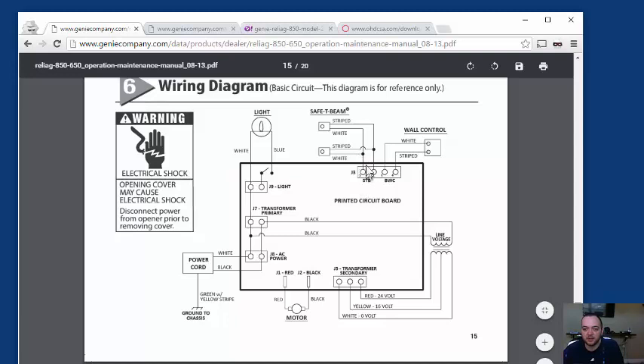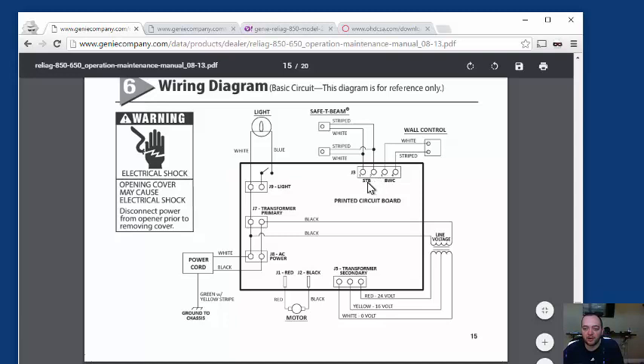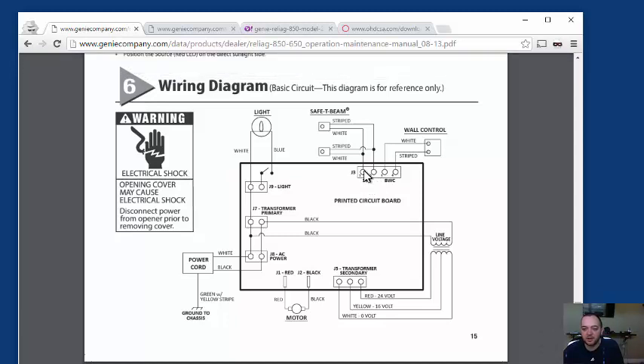It's important to note that these first two pins go to your safety beams. 3 and 4 go to the wall. And pin 1 and 2, it doesn't matter what polarity you hook it up, positive or negative in 1 or 2. These safety beams are polarity neutral. You can hook them up either way.